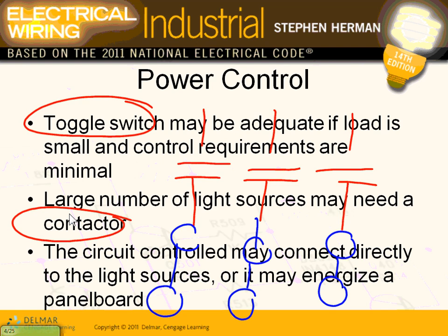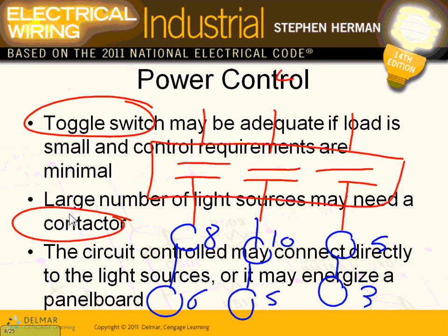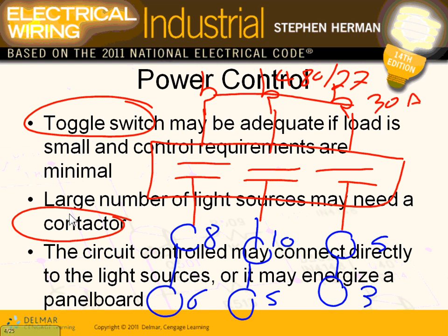Let's say I have five fixtures here, another three here, ten here, another five here, eight here, and another six here. These are all branch circuit loads. This is my contactor, and I'm bringing a voltage of 480/277 here. My overcurrent device is tying them all together. I'm pulling a 30-amp circuit to a contactor, and from the contactor I'm going to all these parking lot lights. This is typical three-phase — you pull a neutral here and each one of these fixtures is burning at 277.